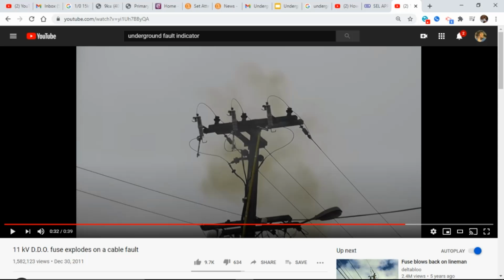Well, they got away from that. One is you're blinking the lights every time you blow a fuse on the line. And two is every time you put a fault on underground primary conductor, it is stressing it. So that's why we went to the high pot method. And there is actually another method we're getting ready to go into in just a moment. But do remember that overhead faults typically clear themselves. That does not mean you do not have to patrol it. If I have a fuse, and we'll just use this one for example, and this fuse is going down this line, you have to take your vehicle or go on foot and walk down and physically view the entire line. If you don't find anything, refuse it and re-energize it. Underground is typically permanent. So do remember that. You obviously have a fault somewhere that you need to find and isolate. Does that make sense? Yes.